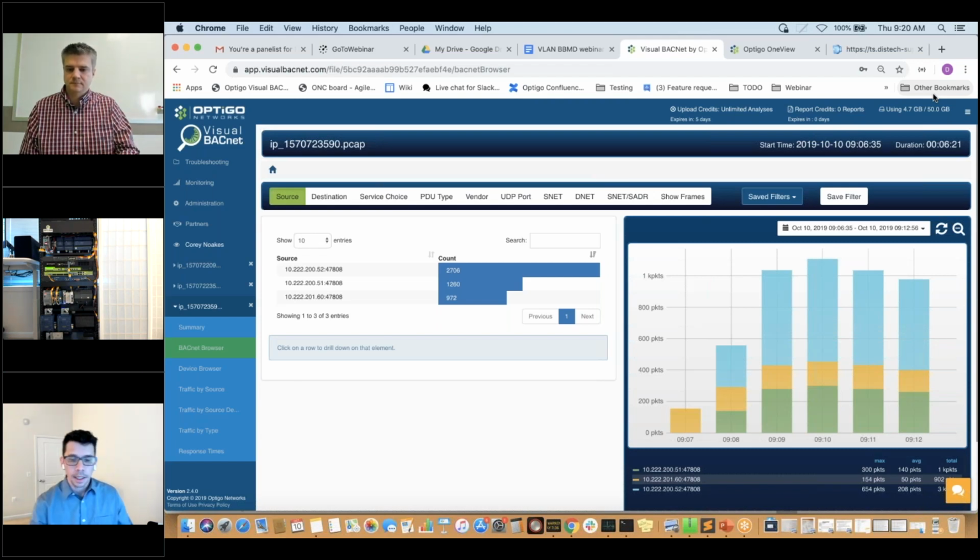And eventually it will easily take down your MSTP trunks. They can be saturated easily. But even on the IP side, we have sites where once you start getting past 12 and 13 and 15 VLANs, you can start taking down the IP side as well. Those controllers can only queue up so much, and so it's really important to look at that from a design standpoint.